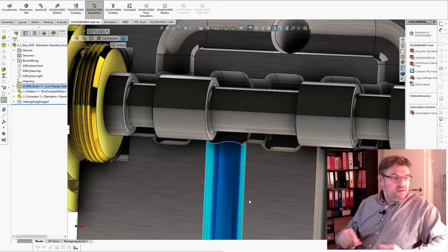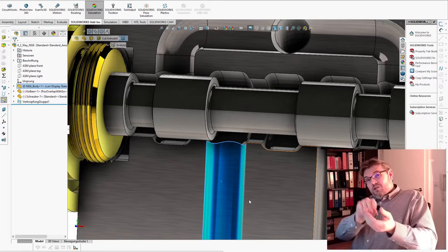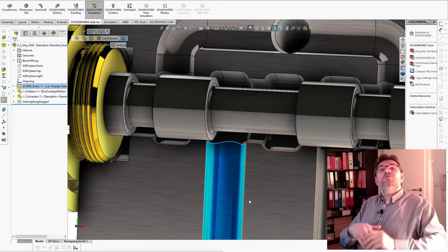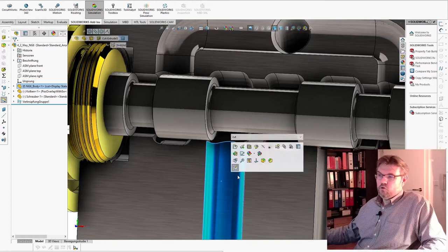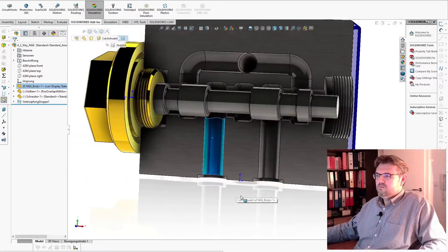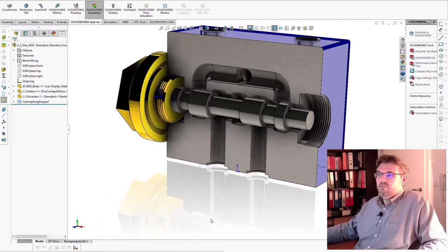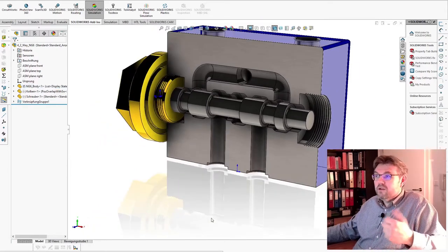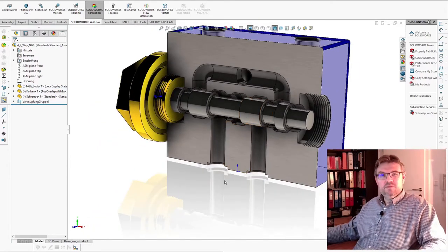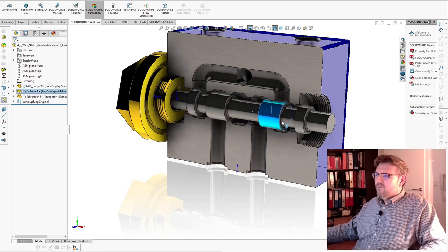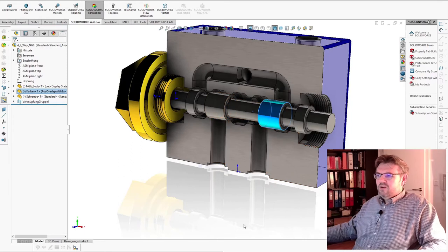And you see, this is just the form of the piston. If you take the same valve and exchange the piston inside, you have a different switching behavior. This is actually really how it is done. Behind the different ordering codes and so on, they are just different pistons. So you see, there are quite a lot of ways things are connected inside there.